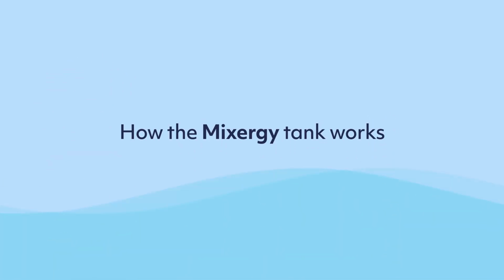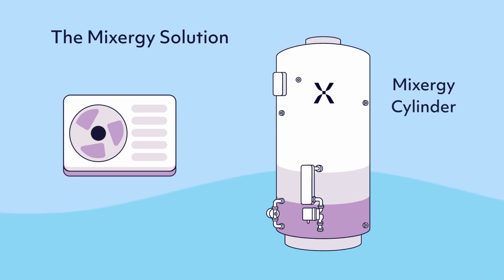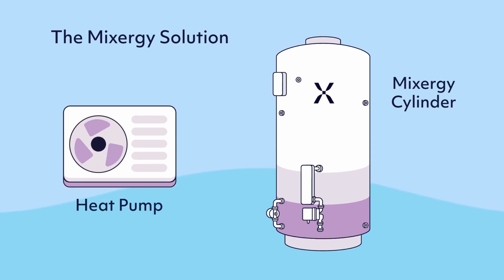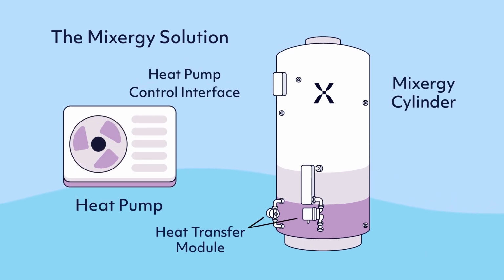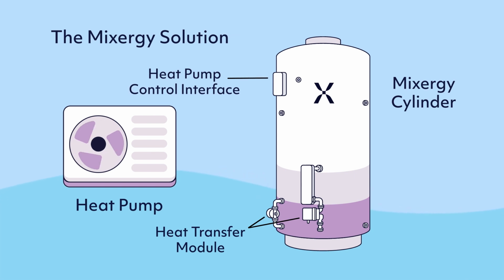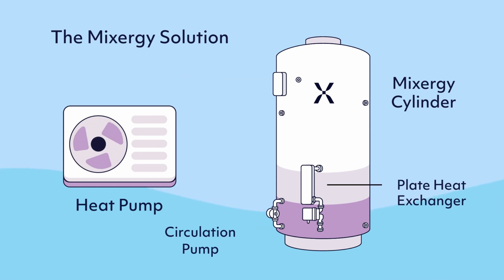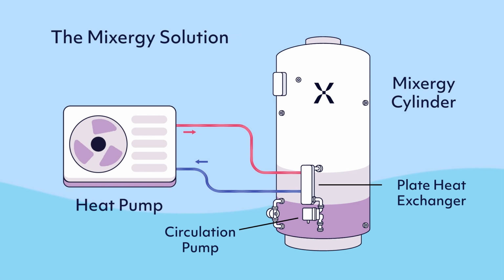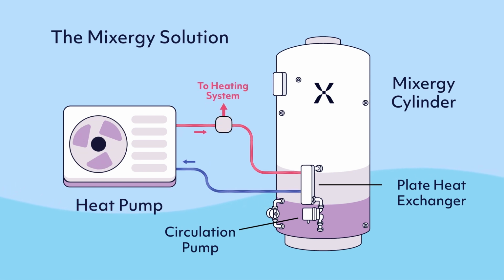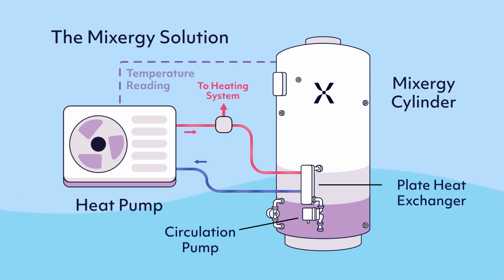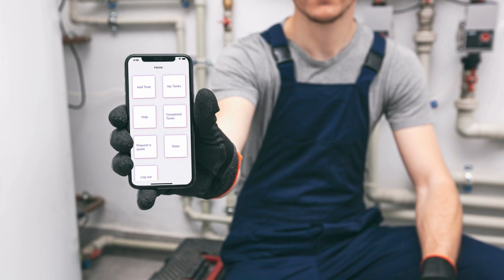At Mixergy, we do things differently. Instead of having a coil inside the cylinder, we have a heat transfer module and heat pump control interface. The heat transfer module comprises a plate heat exchanger and circulation pump. This allows us to transfer energy from the bottom of the cylinder to the system loop. The heat pump interface works with the heat pump's temperature probe to determine when to heat the cylinder, based on the hot water schedule programmed through the Mixergy app.